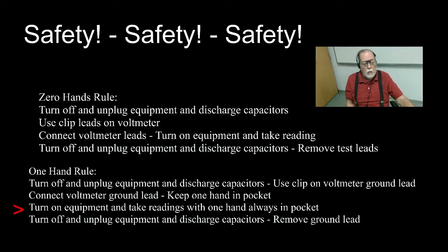When you make measurements, preferably, though difficult, is the zero hands rule. If you're going to measure a voltage, clip your voltmeter leads across the device you're going to measure. Then you turn the unit on, make the measurement, turn it off, and remove the clip. So you never have a hand on a test probe while measuring a voltage.